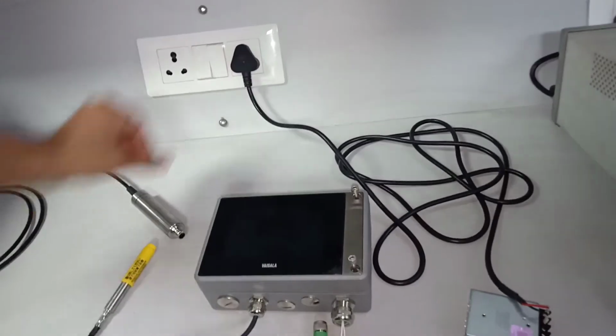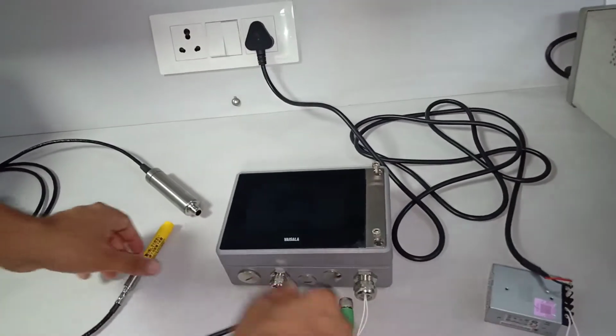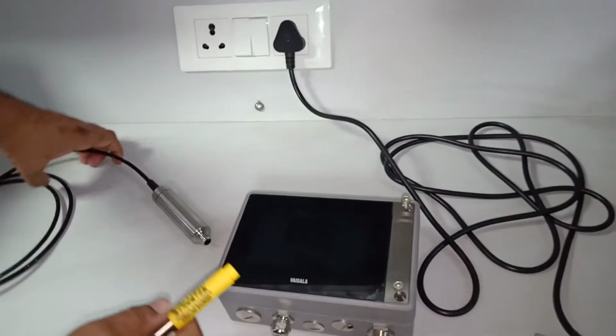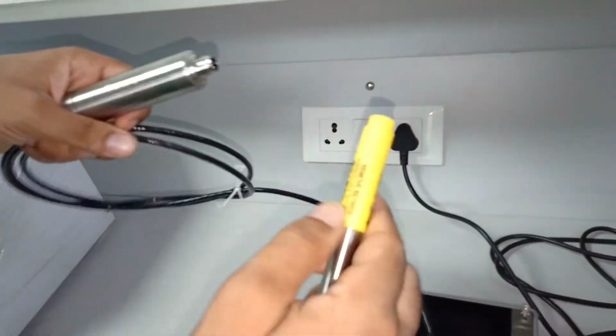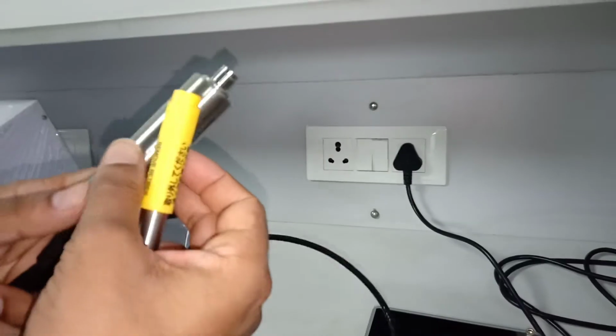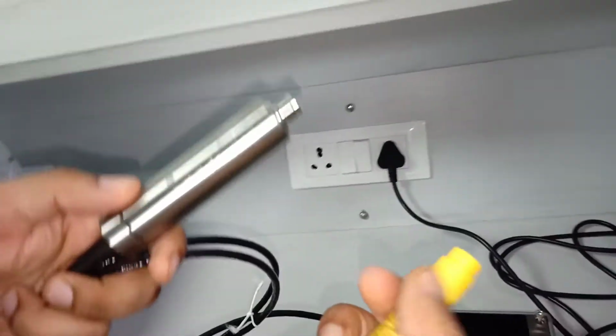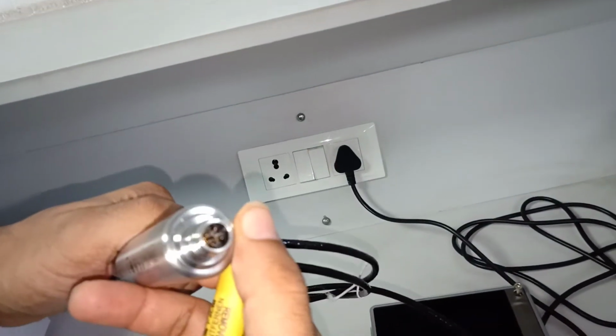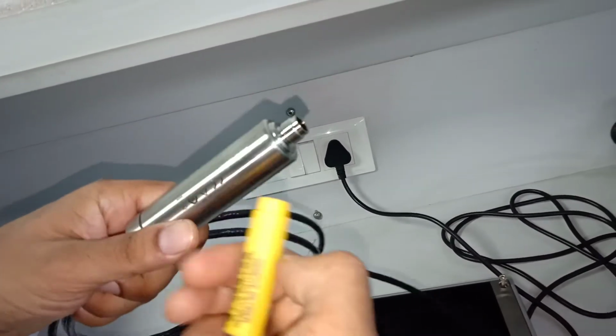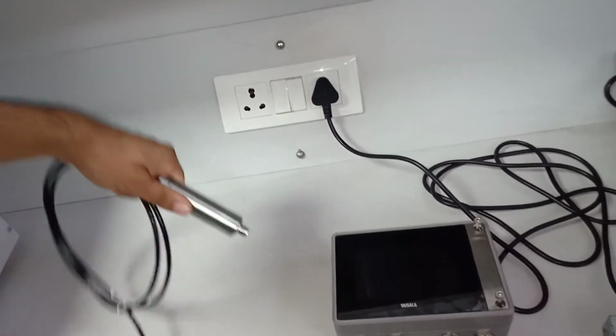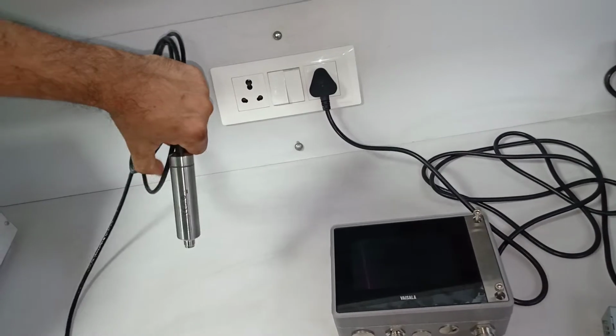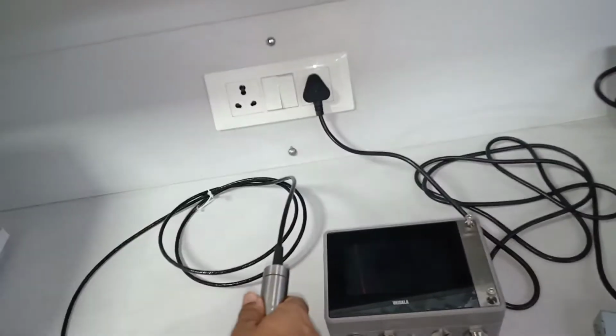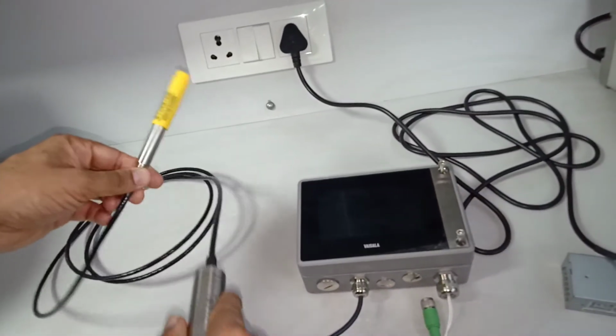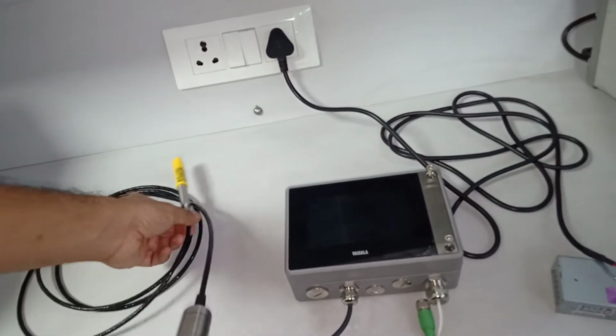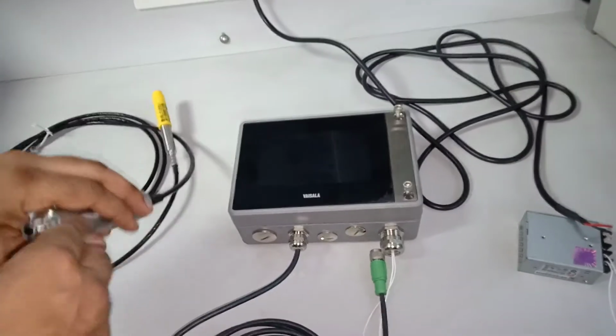So I switch it on. It will take some time to switch it on, so it gets set. This is Vaisala's smart probe HMP3. So HMP3 can be used as a standalone unit. You have this port which gives RS485, so you can directly configure it with your PLC SCADA for taking the readings. We have different probes. So this is for humidity temperature. You can get CO2, hydrogen peroxide probe as well.